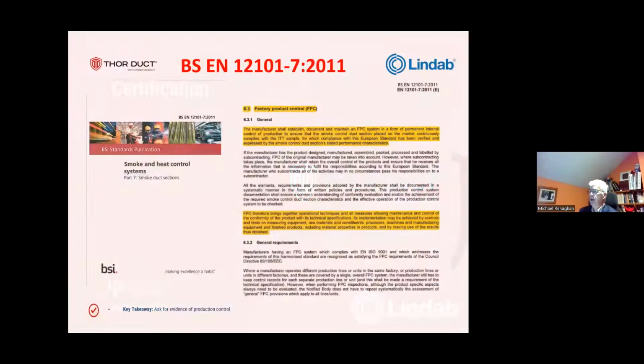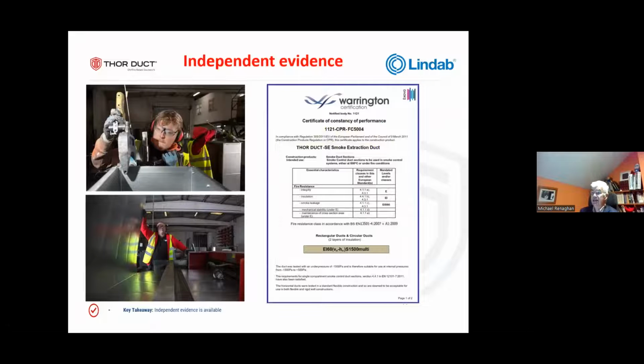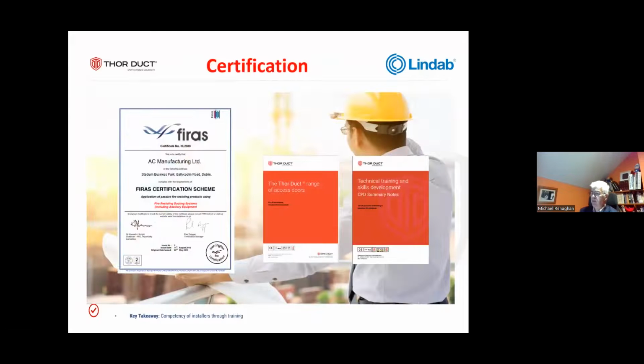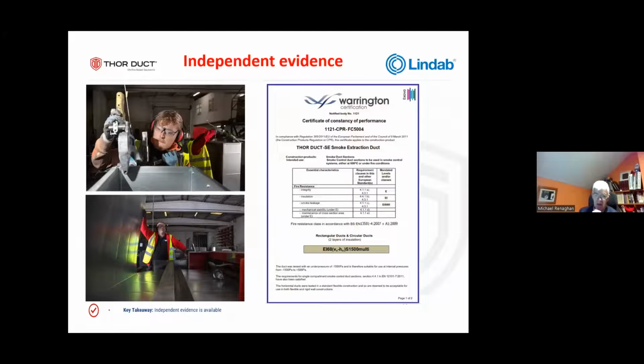From a certification point of view, the requirement in the smoke standard says that there should be FPC, factory production control. That's something the manufacturer has to have in place to provide you with compliant smoke extract ductwork. As a result, they will have a certification and a CE mark. The problem with the existing market is there are products, and we have them as well, that are field installed. So you have the duct, but the insulation is field installed. There are also products that are both insulated and duct coming from a factory where they're CE marked. CE product is a completely different product because it's supervised by a notified body. It's subject to leakage testing.